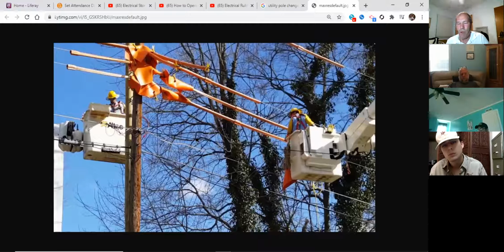But there's one missing component here that we had to cover up also, and I think Professor V notices it too. What would that be, Professor V? Your communications. As far as the utility is concerned, this is secondary, the neutral 120. So they have the secondary wires covered up, the primary wires covered up, about 1, 2, 3, I'd say 4 hoses over here, but there's one conductive component that's not covered up. What is it? Communications. That's a steel wire that runs down through there, and the communication lines are attached to it, going both directions off the pole.